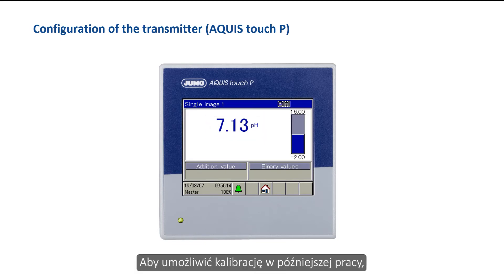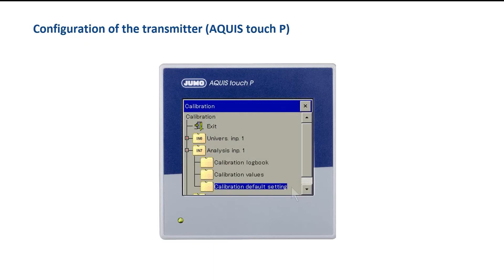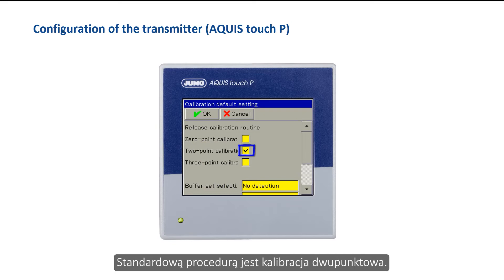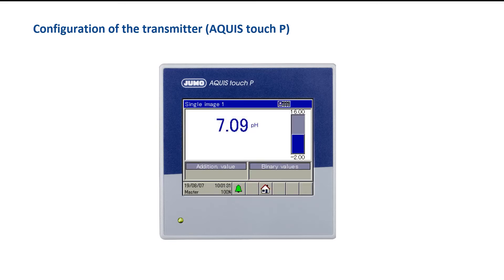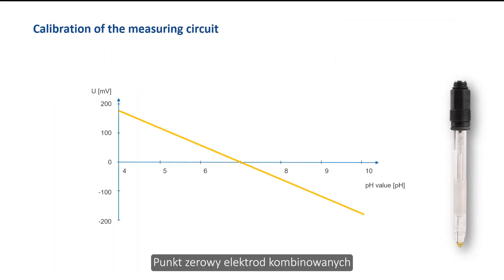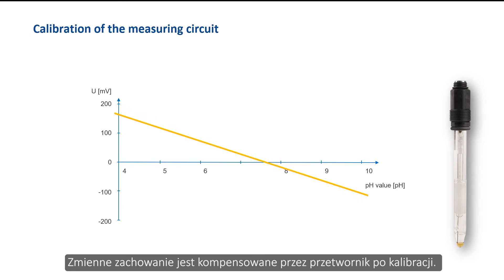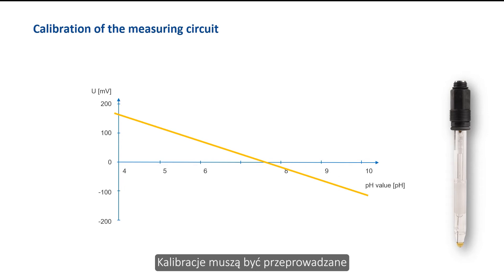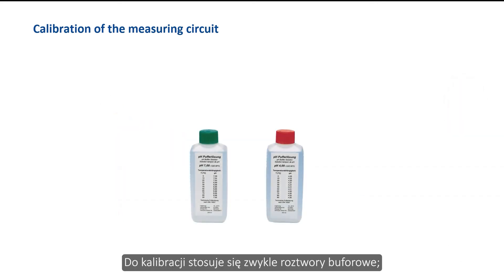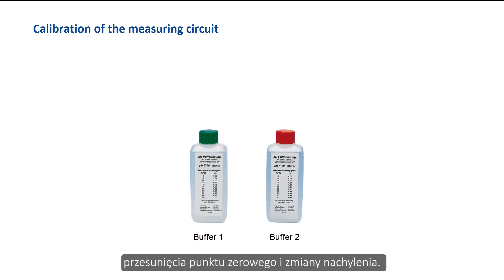In order to enable calibration in later operation, this must be released. The standard procedure is two-point calibration. The zero point of combination electrodes changes during their lifetime and the slope also varies; this changing behavior is compensated by the transmitter after calibration. Calibrations must be carried out at new start-up and periodically during the lifetime of the electrodes. Buffer solutions — liquids with a defined pH value — are used for calibration. Two-point calibration compensates for both zero-point shifts and slope changes.